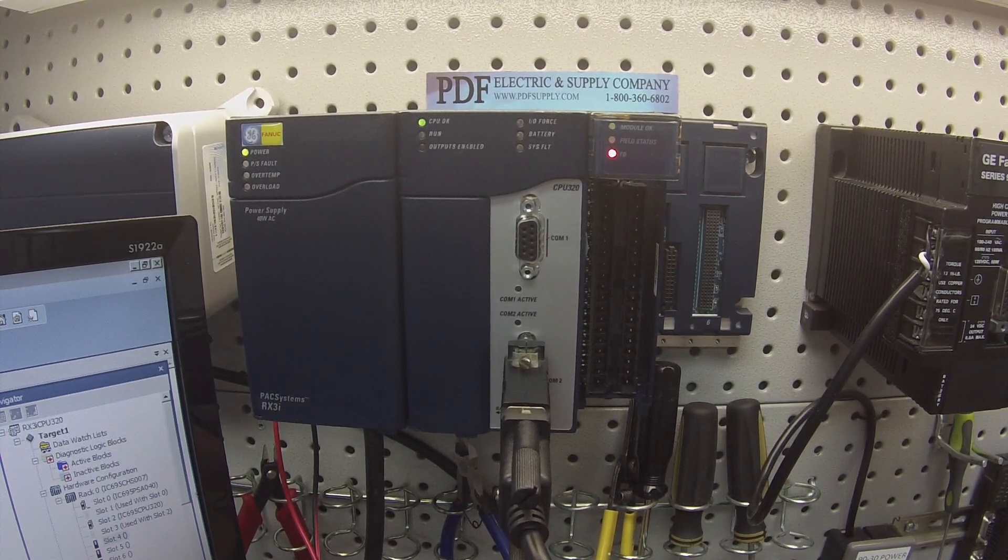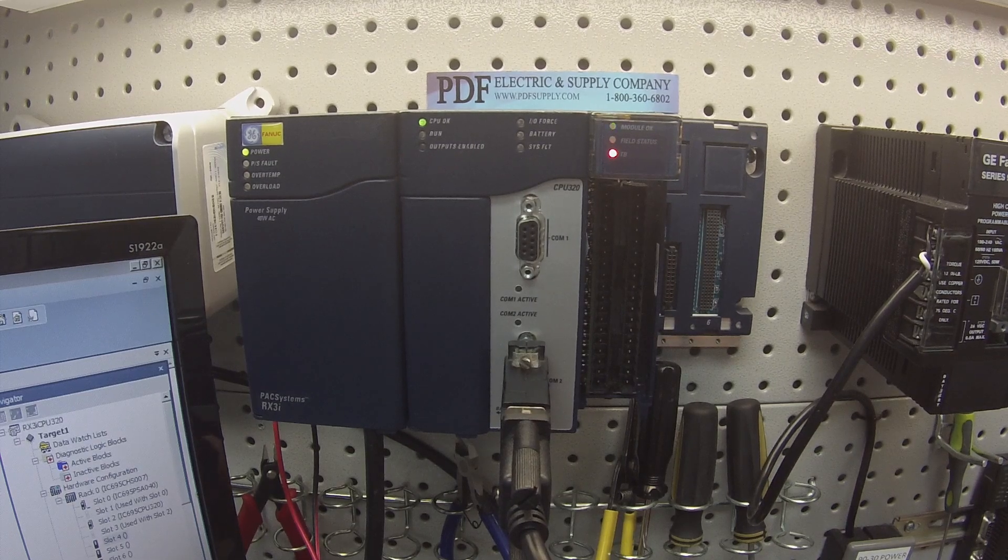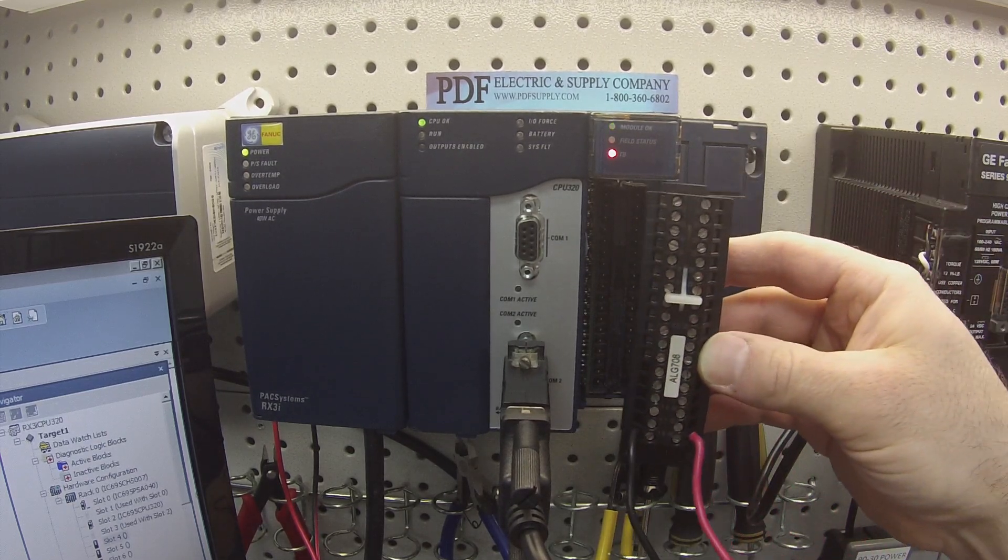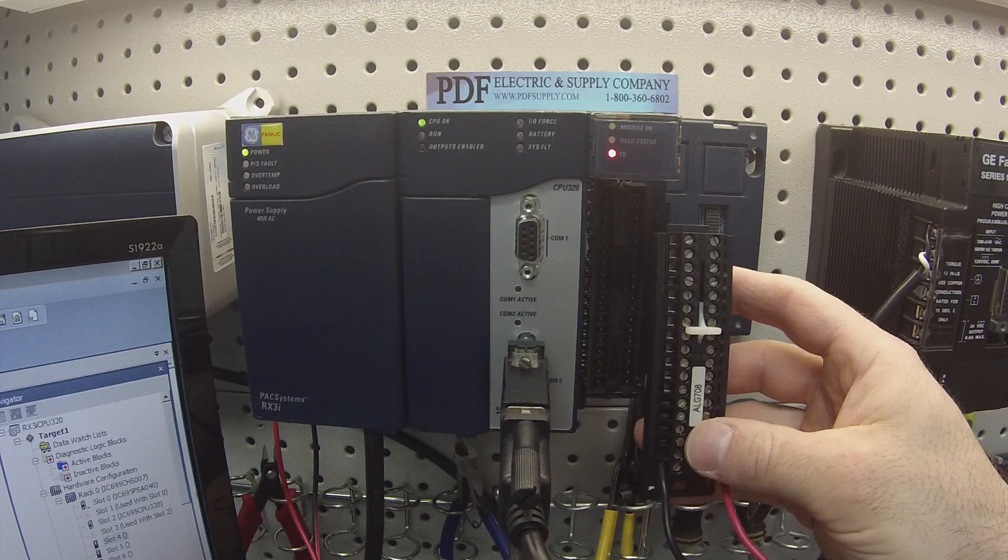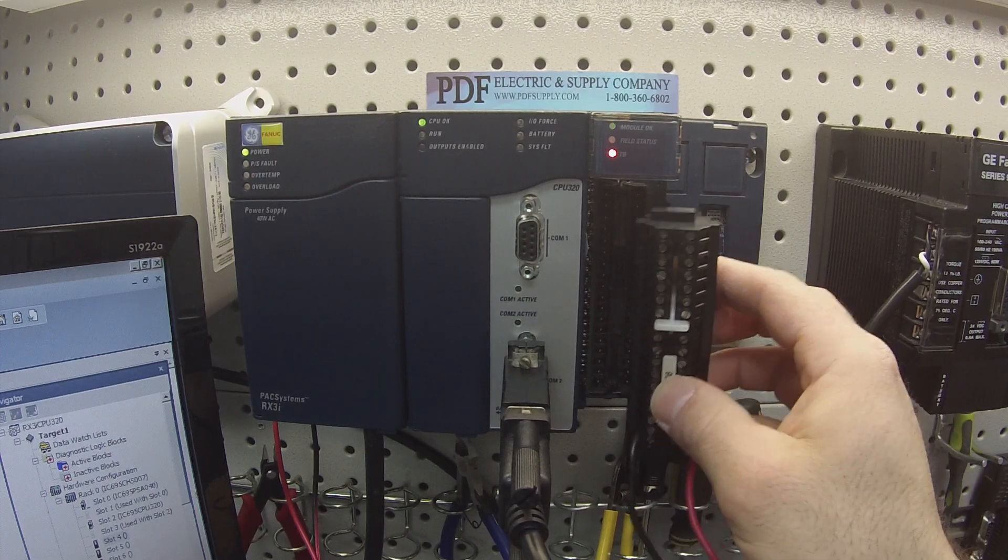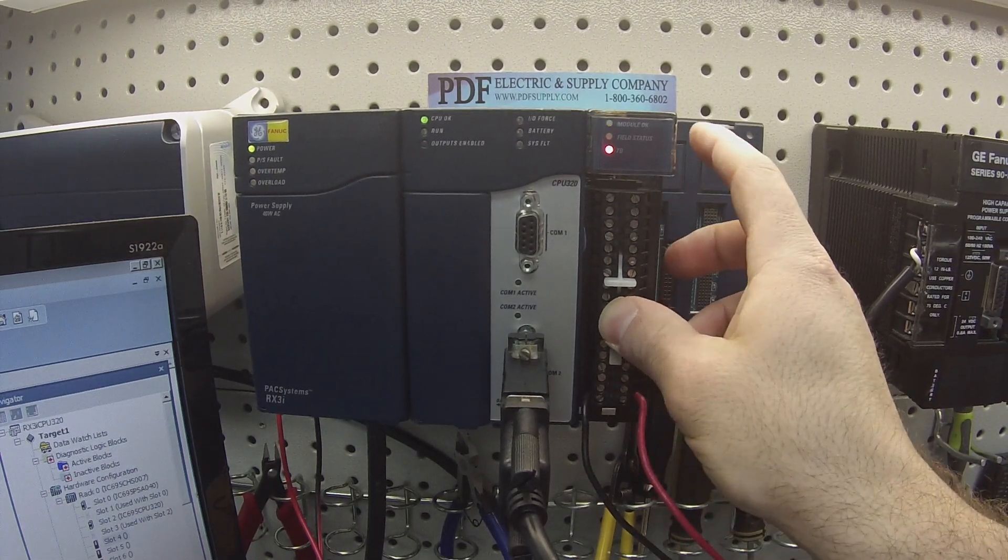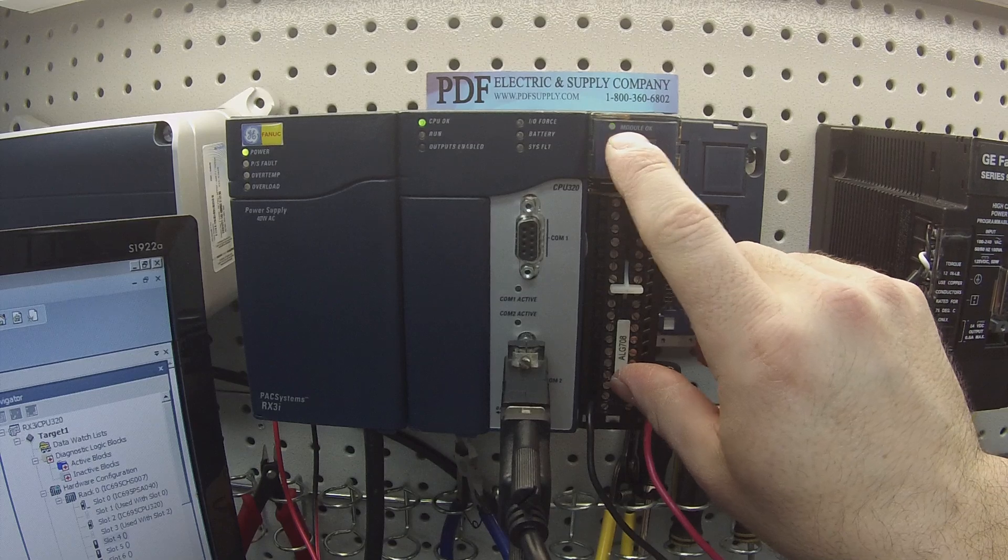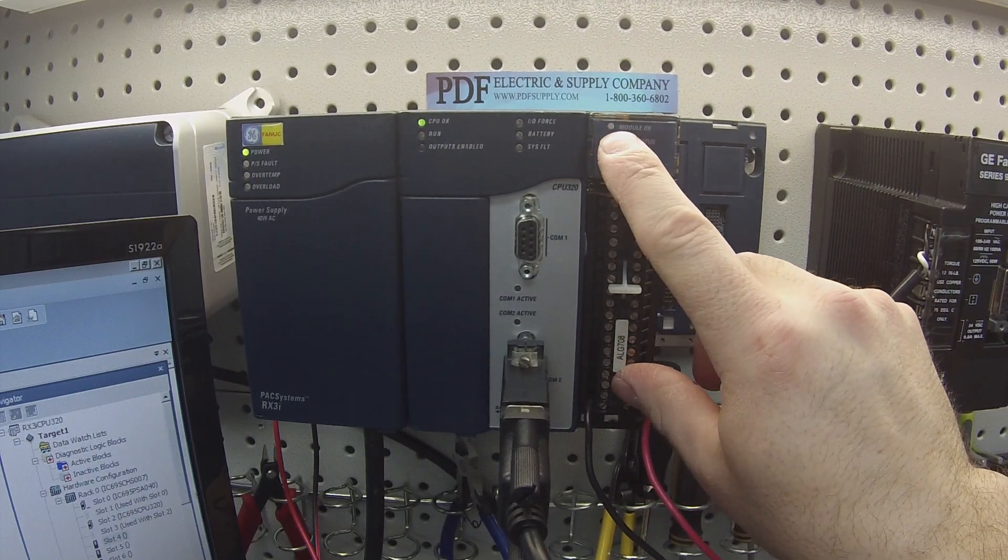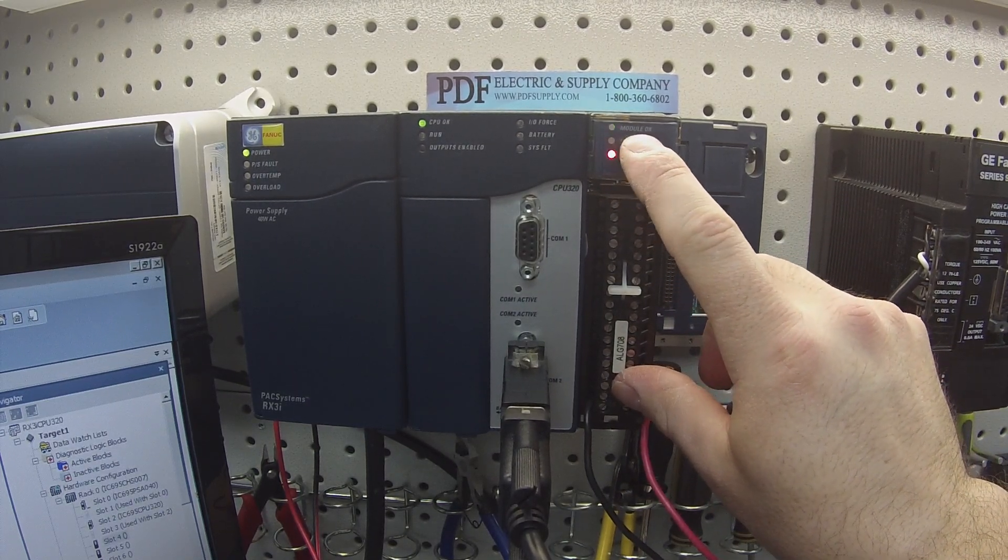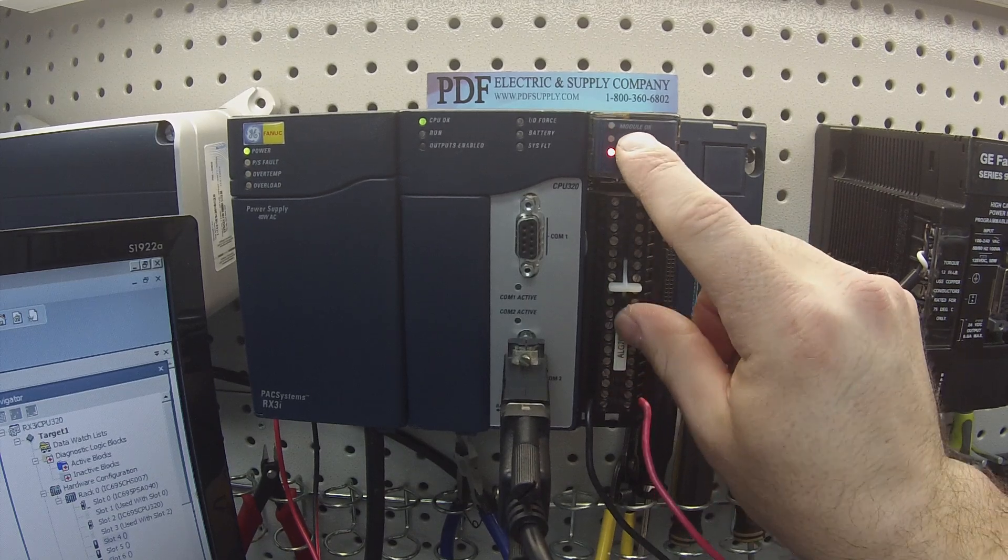The first thing I want to show you is the terminal strip is a high density terminal strip. There's 36 terminal screws on this particular one. When we attach it, the first thing that we want to do is look at my light pattern here. You should have a green blinking light if it's a good working module.